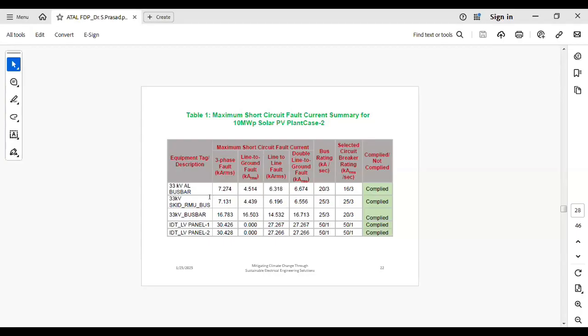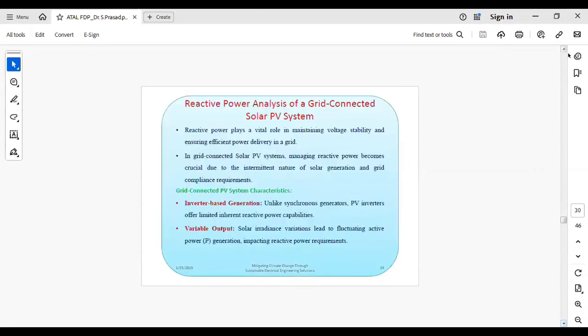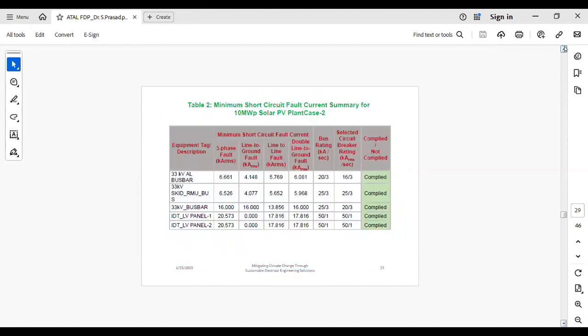You can also verify for the 33 kV buses: the three-phase short circuiting current is 7.274 kiloampere and 4.514 kiloampere, which is very much less compared to the LV panel bus. So based upon this, you have to design the circuit breaker rating at the LV panels and at the 33 kV buses. Therefore, the short circuit test is conducted. And this is the minimum short circuiting current, which is required. The minimum value is also required for the relay coordination study. So we are conducting both maximum as well as minimum short circuiting current analysis.